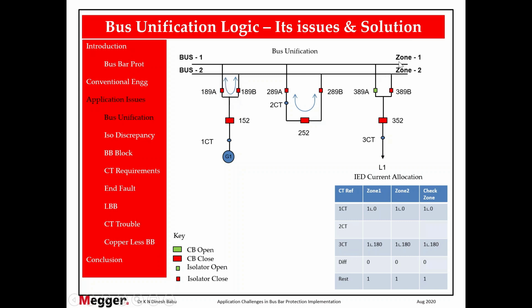Because even if a zone 1 fault occurs, even if you open the bus coupler, zone 2 will still be feeding through this path, because it's only an isolator and there is no breaker mechanism available to eliminate the faulty part. So the moment any two isolators are closed, it is a single bus arrangement. So you have to trip the entire zone. That is why this concept is implemented in this way.